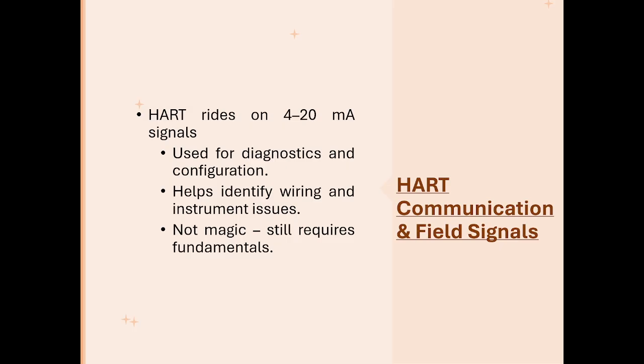We have HART. HART is a communication protocol used with many field instruments, and HART stands for Highway Addressable Remote Transducer. In simple terms, it allows digital communication to ride on top of the traditional 4 to 20 milliamp analog signal. If you're new to automation and instrumentation, hearing 4 to 20 milliamps may sound strange to you, but these are analog signals. So a digital signal is riding on top of an analog signal. That's what the HART communication protocol does. This means we can read diagnostics, configure instruments, and verify settings without removing the instruments from service.